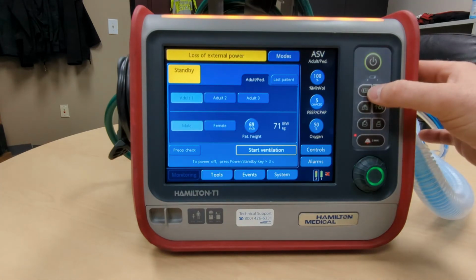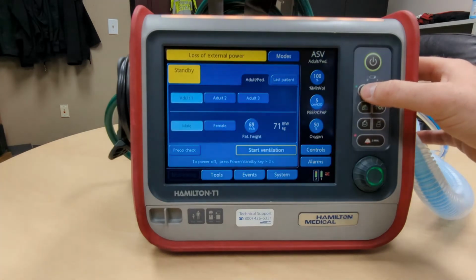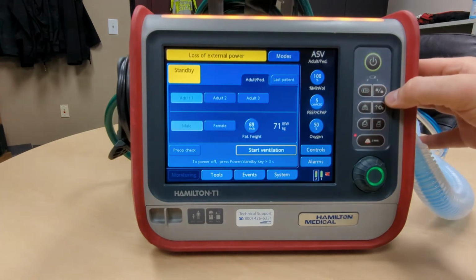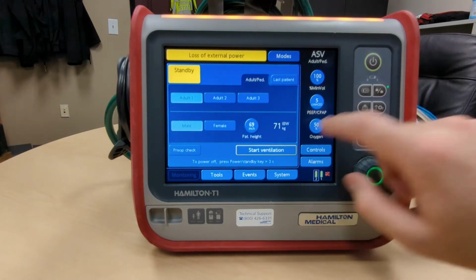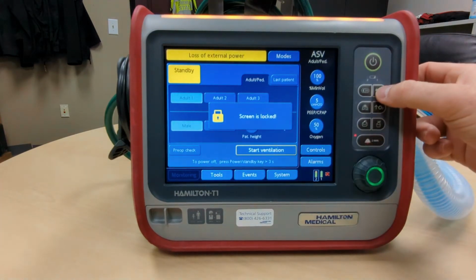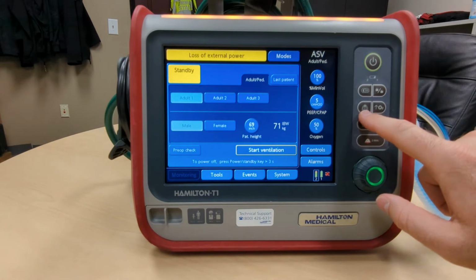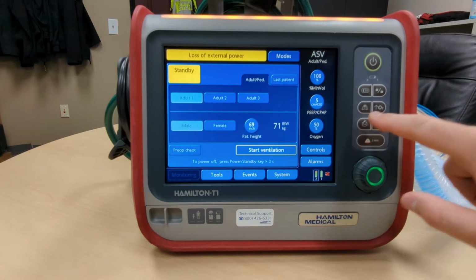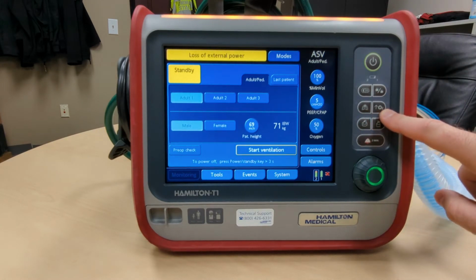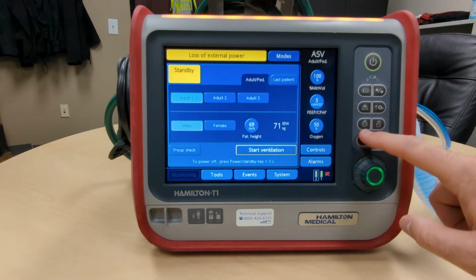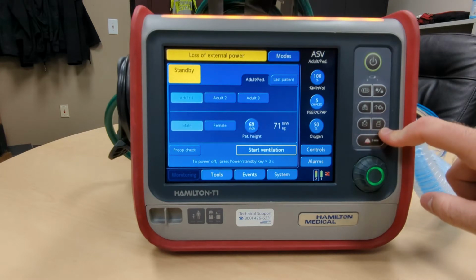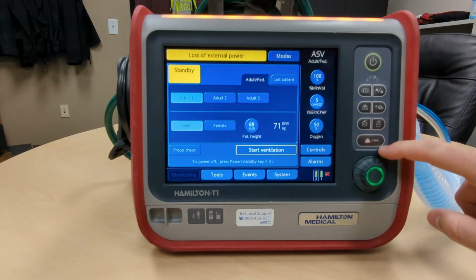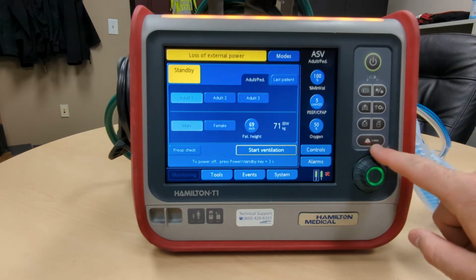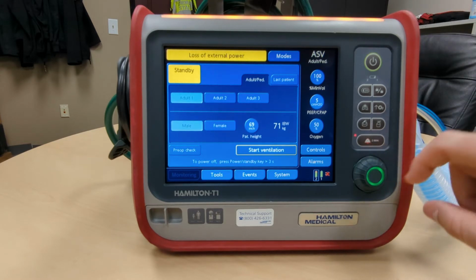This is the daytime night operation screen. The lock screen button. When ventilating, this will do an instantaneous hold. This will increase the oxygen percentage to 100% for 2 minutes. If you have a USB attached, this will do a screenshot when pressed. This is the nebulizer button, and this is the alarm silence button. As it says here, it does a 2-minute alarm silence, and this is the magic wheel.